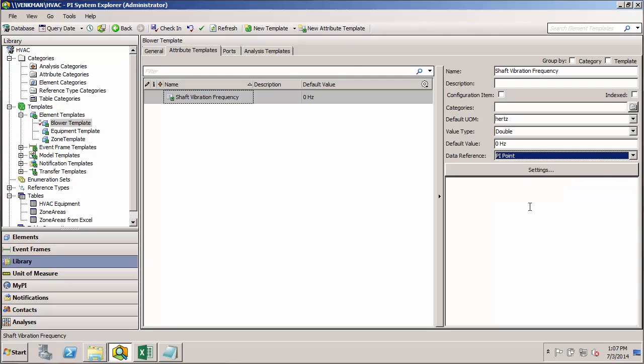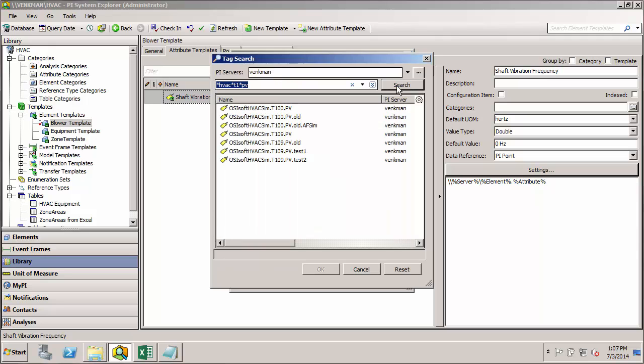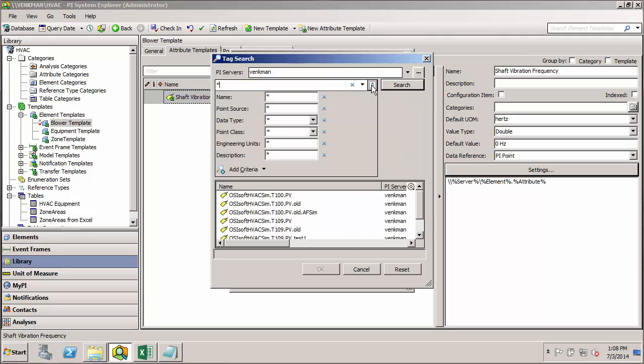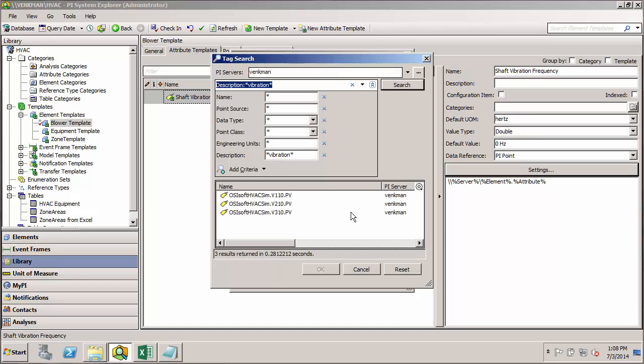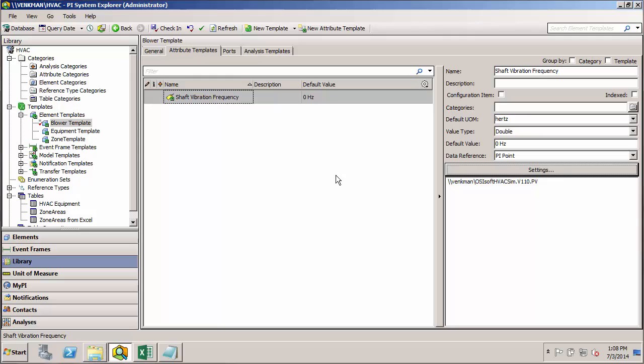And this is a PI point data reference. Let's see if we can find one of our tags for that. So I'm assuming it has a similar naming convention to the temperatures and power usage and status, but I don't really know what the letter code here would be. So rather than searching by the name, let's see if I can search by the description and maybe they've put a description in their tags that'll help us out. So we'll try any description that contains vibration. Do a search and it looks like they used V as the letter code for the tags. So we'll just use the tag for zone 1 blower. Hit OK.